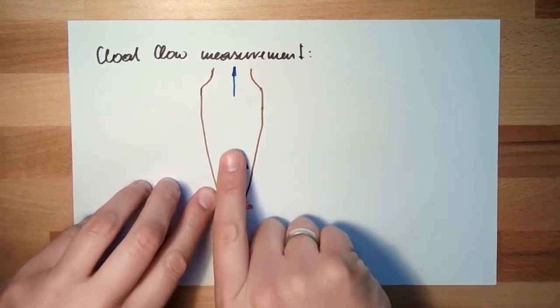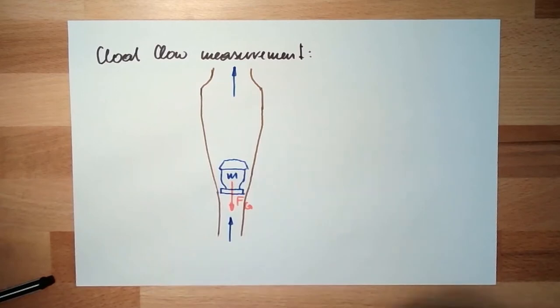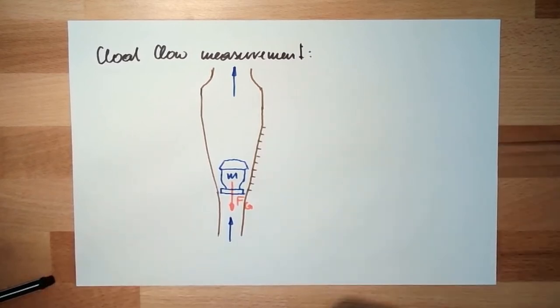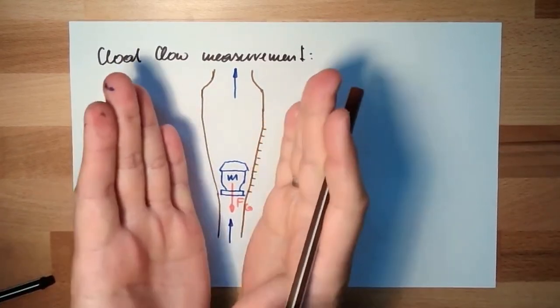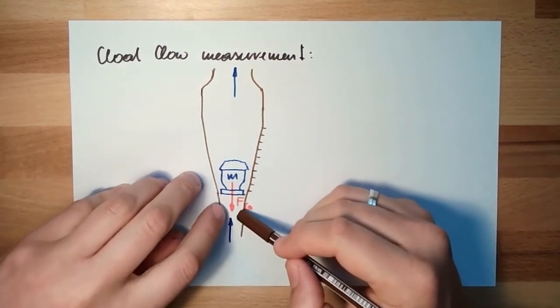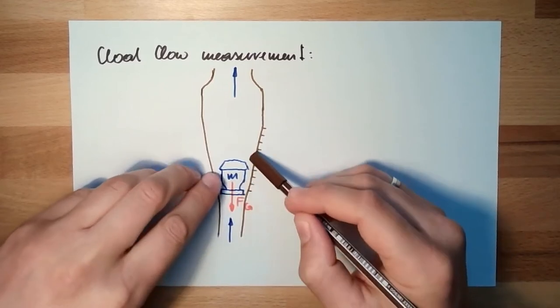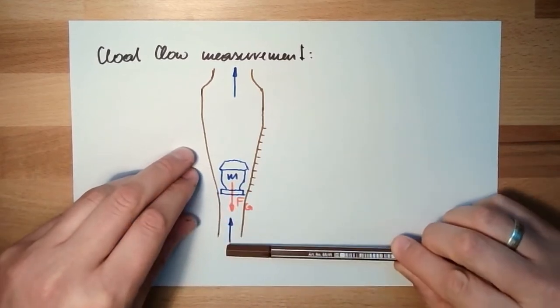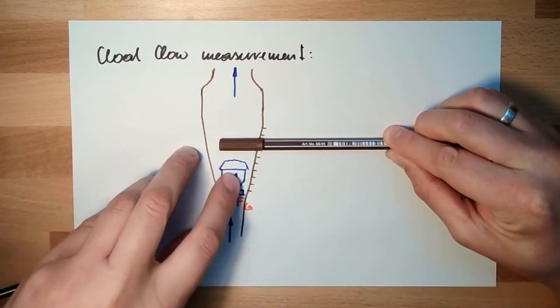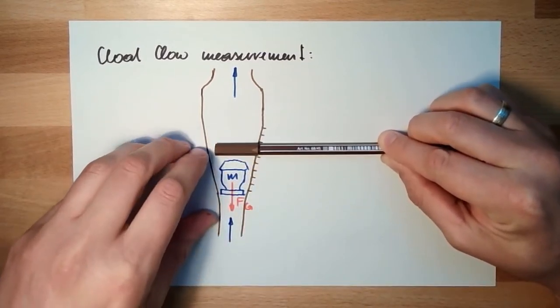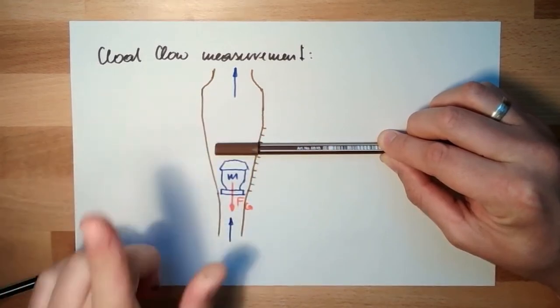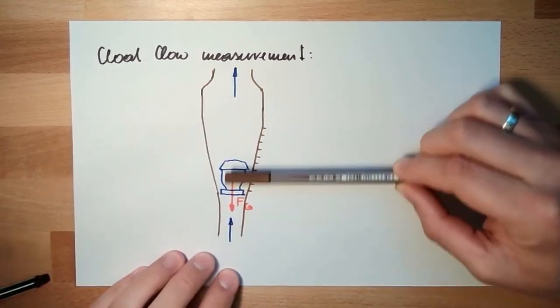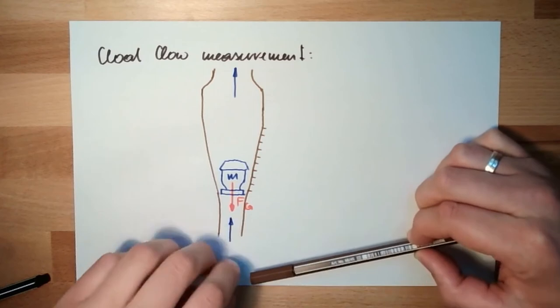This float will start to rise. There's a scale here. Because it's conic, it will get easier for the liquid to pass, so the force of the liquid will drop. The more flow there is, the more this float will rise. When there is equal force in both directions, it will stop. This means the position of the float is indicating the flow rate, and this is what we want to measure. Float flow measurement - very easy.